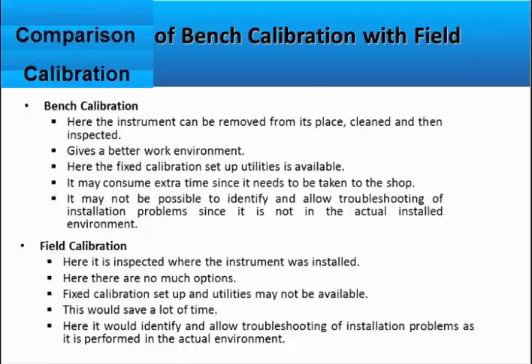One is the bench or shop calibration. It is generally done to a higher specification level, mainly because the instruments it is compared against tend not to be portable. The higher the accuracies are, the more sensitive they tend to be, and it generally takes a lot more time, because the instrument has to be physically disconnected, placed in a suitable container, then transported to the part of the shop or the bench, and then calibrated against the higher accuracy level.